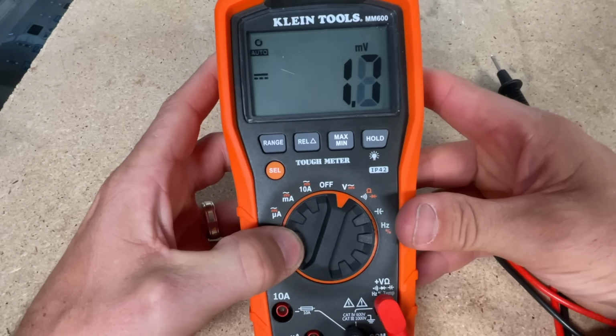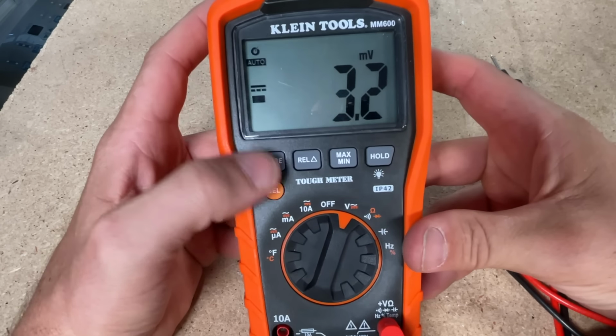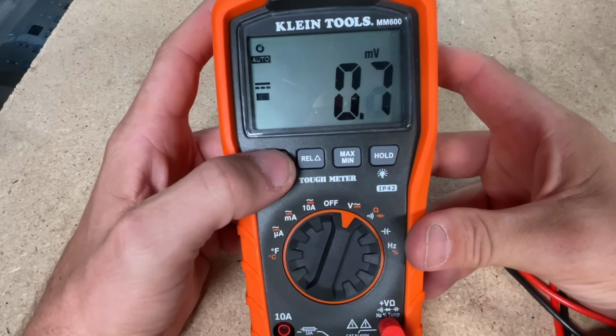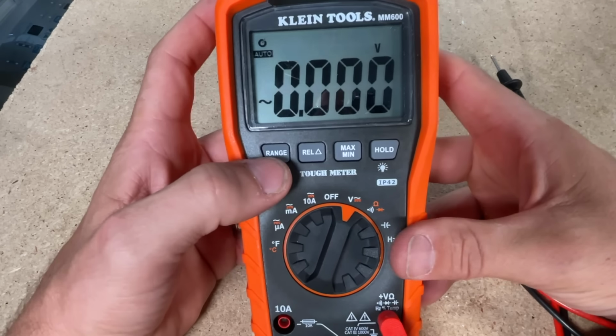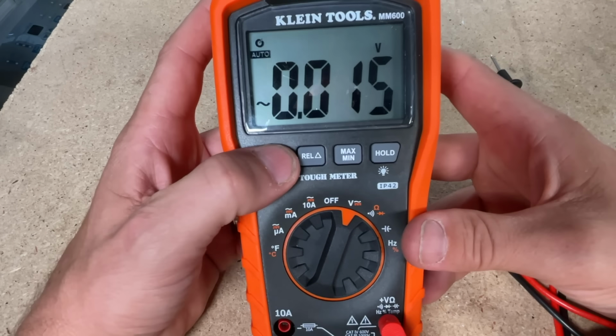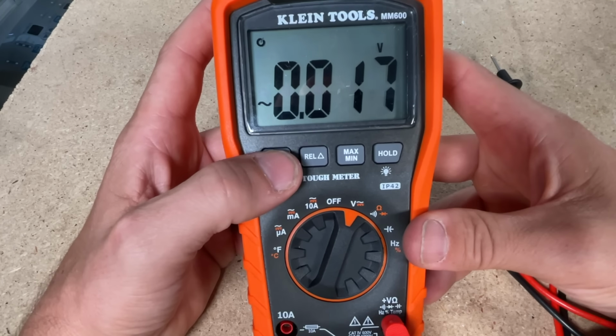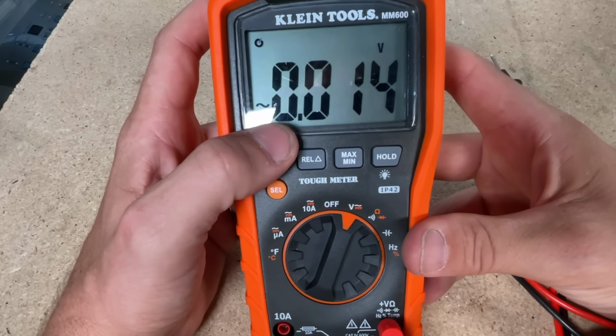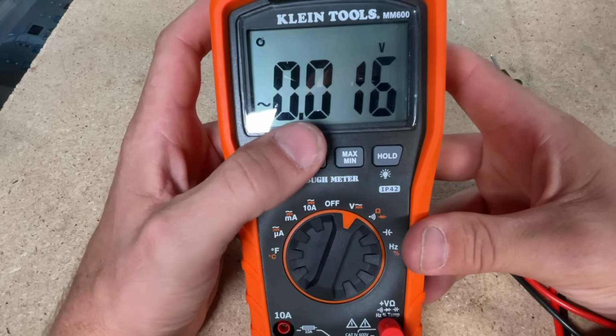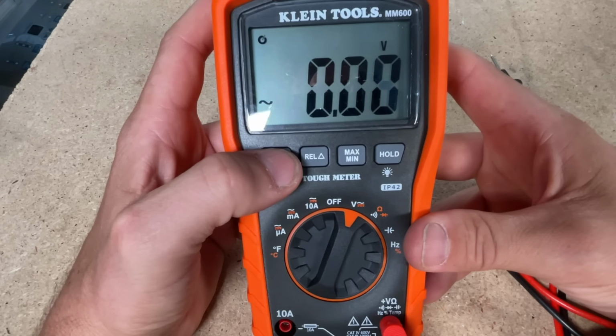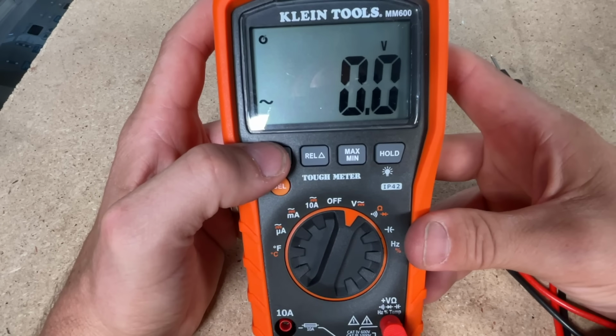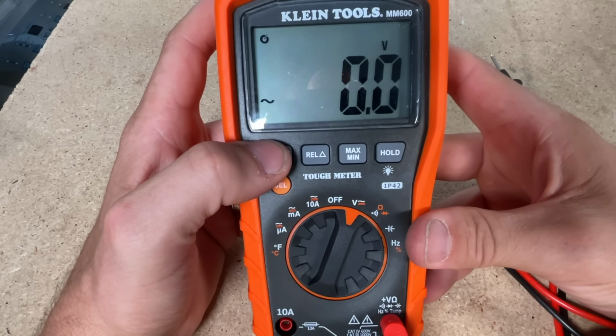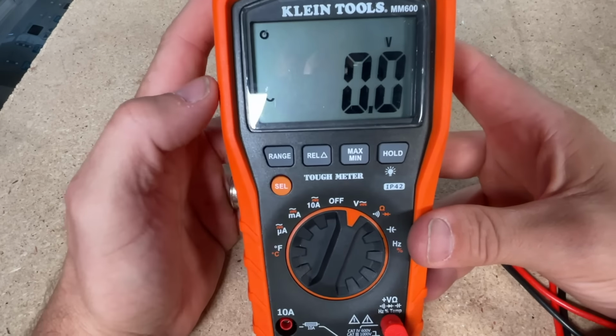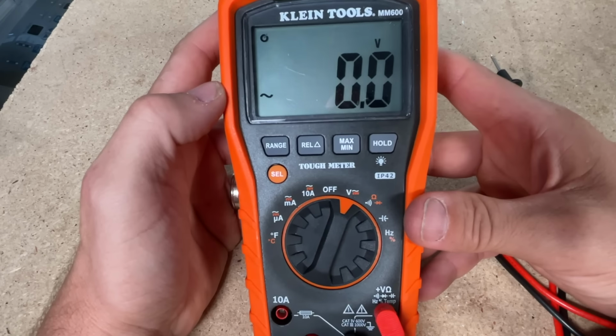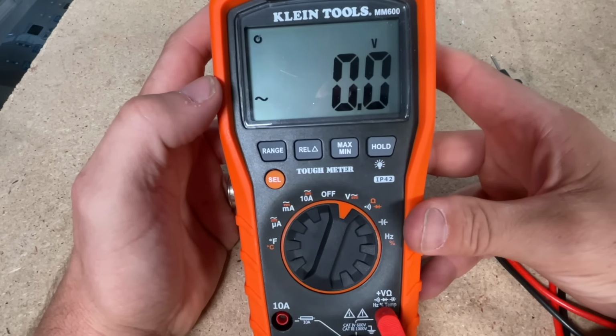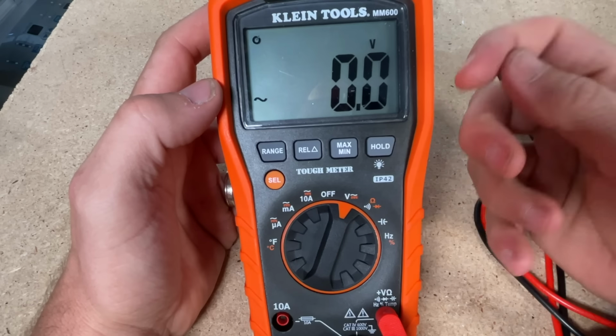Back to the MM600, if you want to auto range, that's fine. You can also set your own range. Off auto, this would max out at an AC voltage of 9.999, this would be 99.99, and this would be 999.9. This is what I'd use to measure at an outlet on a 120 circuit - this would be the correct range if I was setting it.